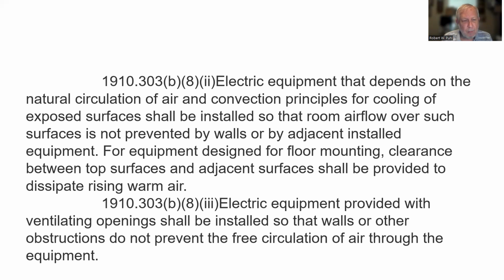Electric equipment provided with ventilating openings shall be installed so that walls or other obstructions do not prevent the free circulation of air through the equipment. In other words, don't butt these up against each other. Leave some space so you can get some airflow if they have vents in them.